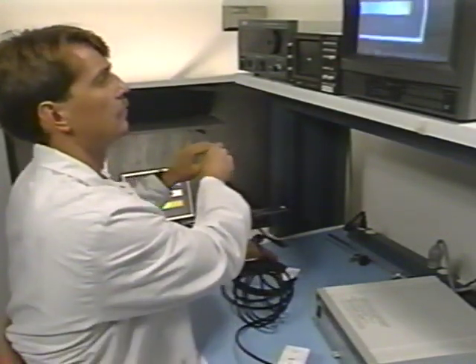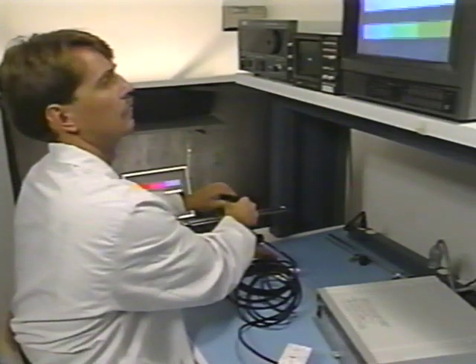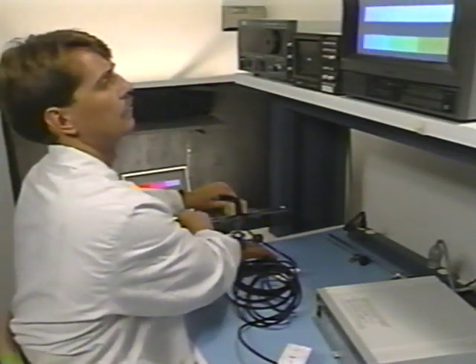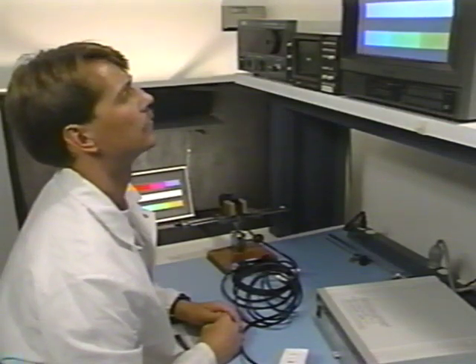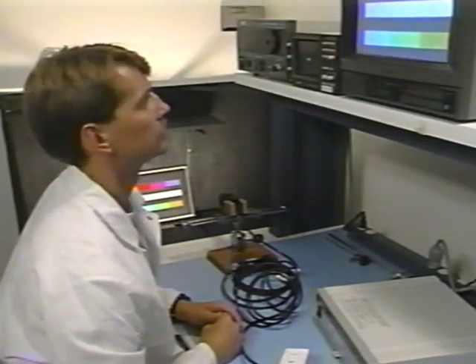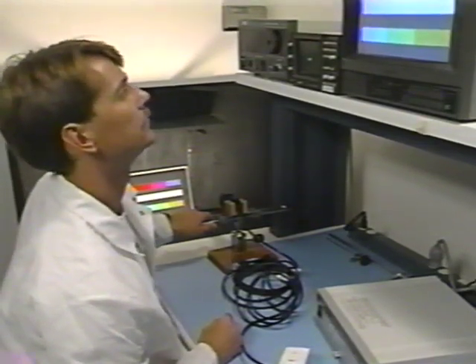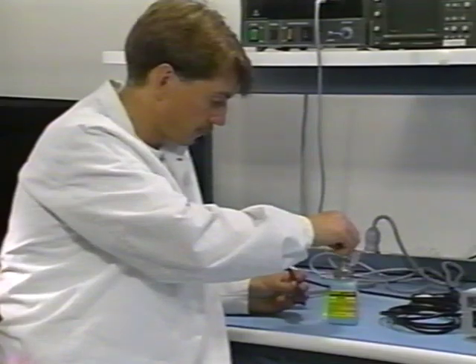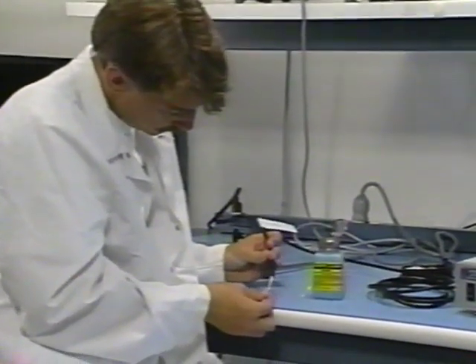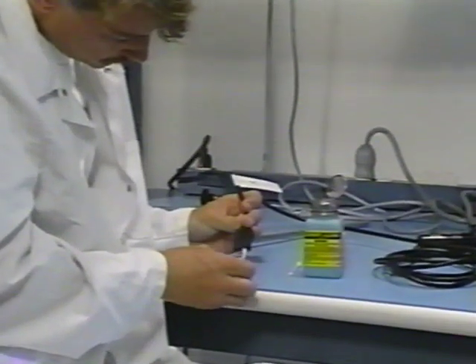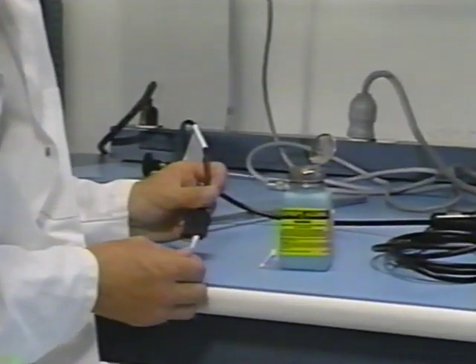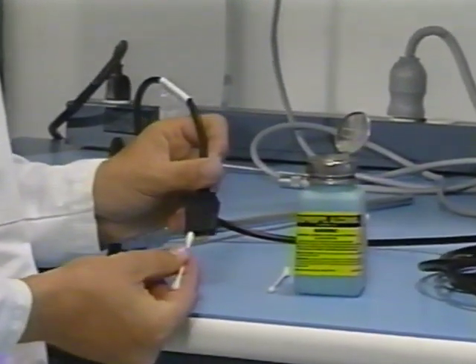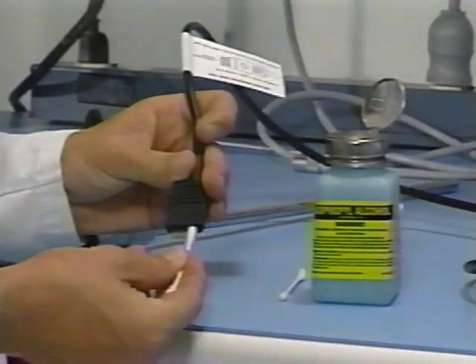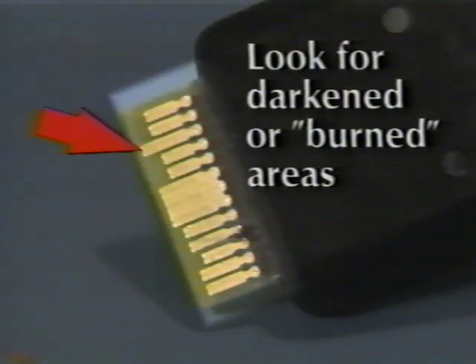Swap camera heads if a second head is available. If the same problem exists with the second head, the problem is likely to be in the CCU. If the initial problem is no longer evident with the second unit, the problem is likely to be in the camera head. Check the camera cable connectors and the connector input on the CCU for corrosion buildup due to improper cleaning techniques following disinfection or sterilization. If corrosion exists, clean the connectors with a cotton swab and alcohol solution. If discoloration cannot be removed and appears to be burned, the connector has shorted out and the cable needs replacement.